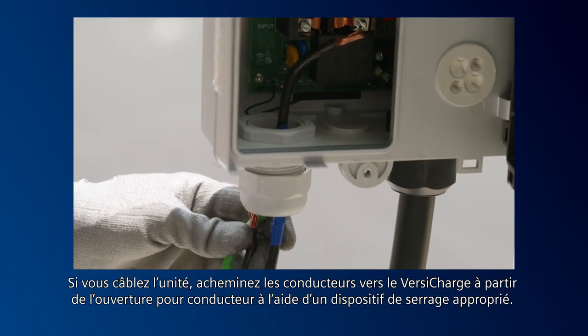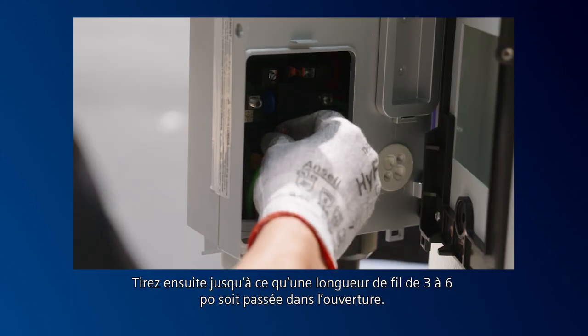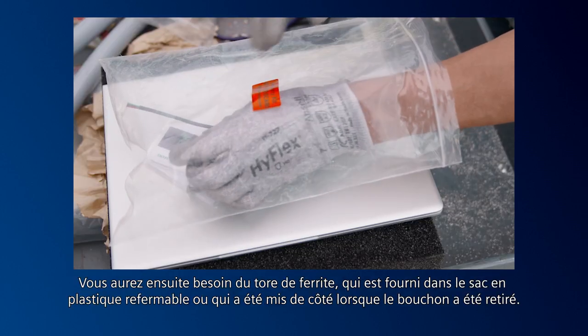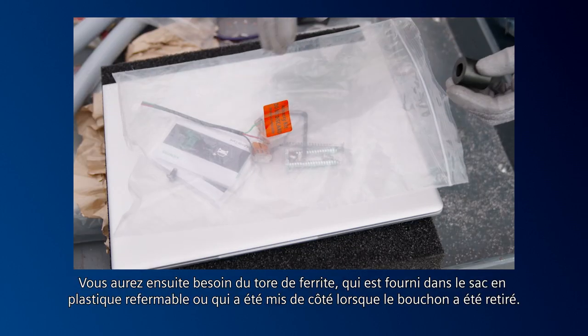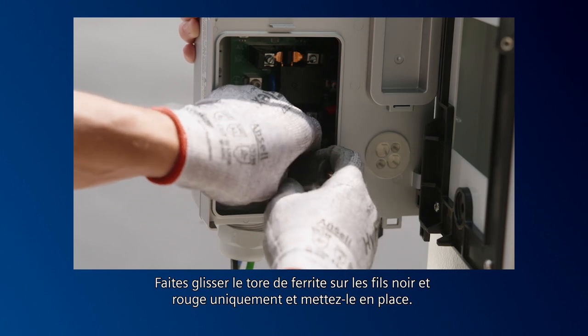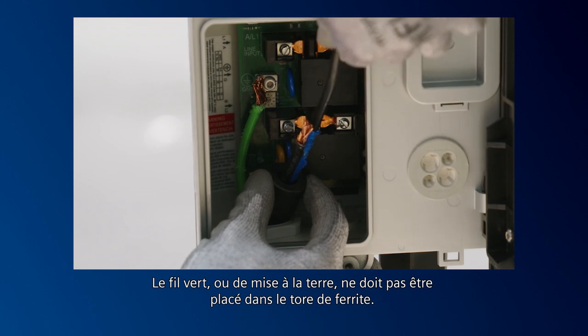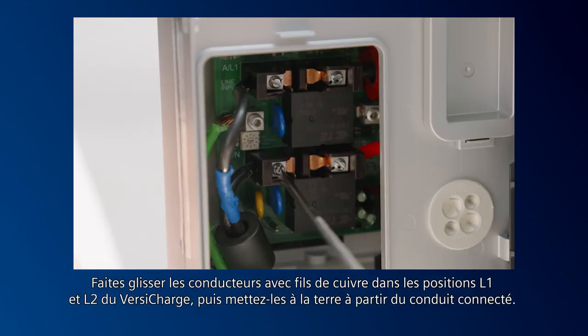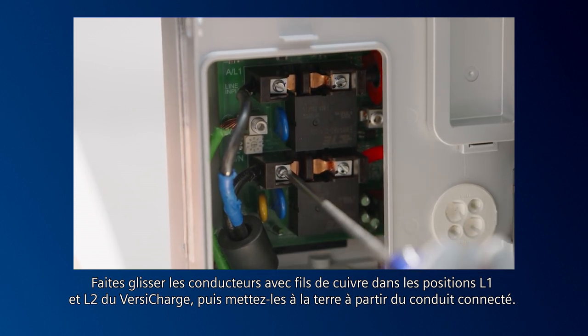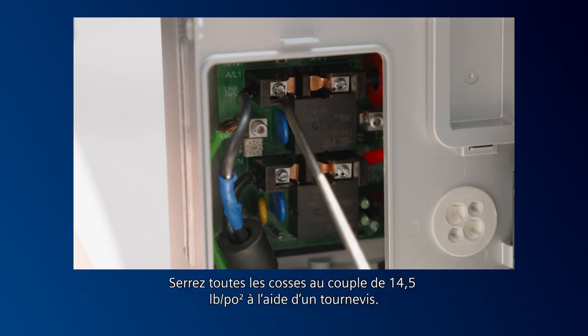If hardwiring the unit, route conductors onto the VersiCharge from the conductor opening with proper strain relief, then pull 3 to 6 inches of slack through the conductor opening. Next, you'll need the ferrite core, which is supplied in the resealable plastic bag or was reserved when the plug was removed. Slide the ferrite core over the black and red wires only and into position — the green wire or ground should not be placed through the ferrite core. Slide the copper wire conductors into the VersiCharge L1, L2, and ground from the connected conduit. Torque all lugs to 14 and a half pound-inches with the screwdriver.